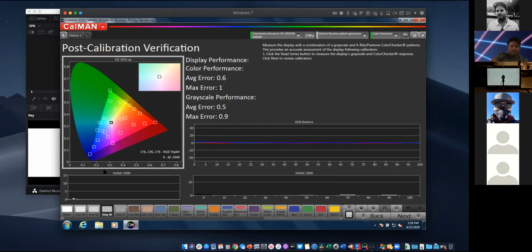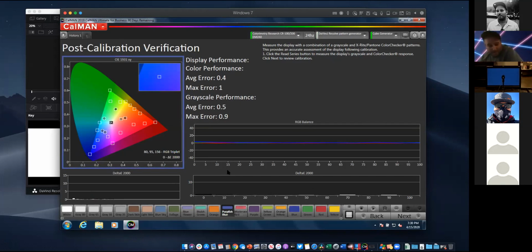Now we're going to do our volumetric check. I'm going to see how those perform. Are those numbers good, Brom? Just for the people that don't know, when the graph looks broken, it's good. With Delta E 2000, typically anything 1 or less is considered not a discernible difference. The normal threshold that is, as an industry, usually accepted for SDR is as high as 2.6.